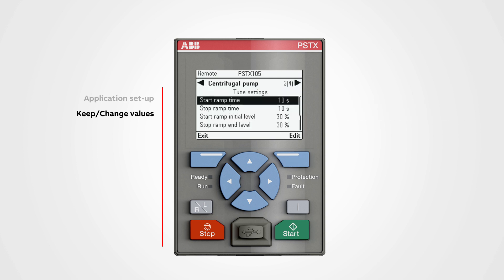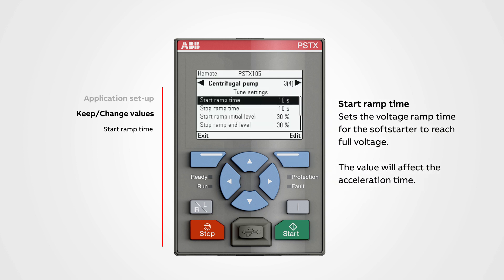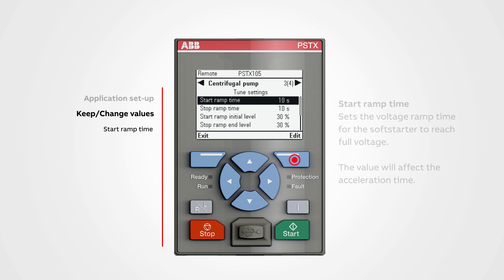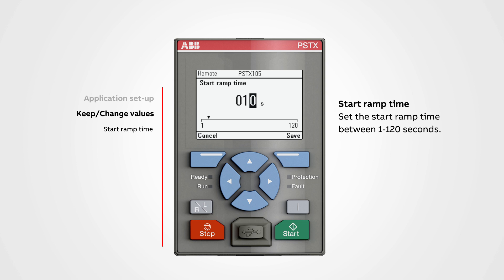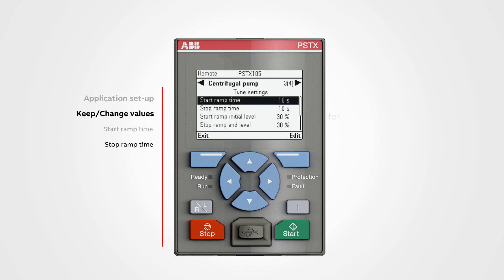Start ramp time sets the voltage ramp time for the soft starter to reach full voltage. A low or high value will affect the acceleration time — with a higher value the acceleration time will be longer, and the opposite if you enter a low number. To change a value, push edit. We can set the start ramp time between 1 to 120 seconds. Use the navigation buttons to change the value, then push save.